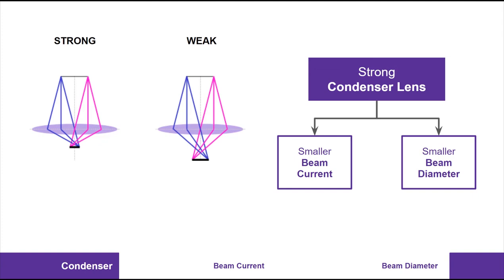At the same time, the condenser lens will also control the beam diameter. The beam diameter at the source is the same for both the strong and weak lenses. Once the beam is focused by the condenser lens, the beam has a new effective size. A stronger deflection will result in a smaller beam diameter. This also means that beam current correlates with the beam diameter. If you want a smaller beam spot on your sample, you will need to use a smaller beam current.